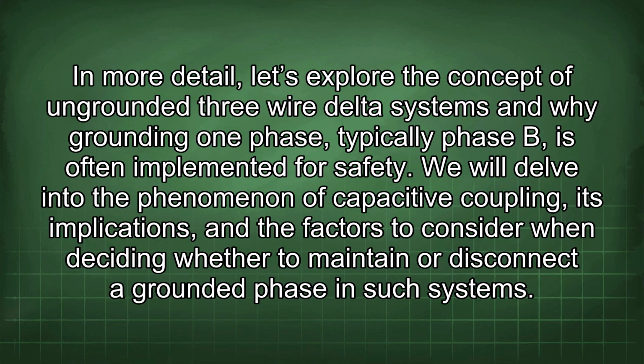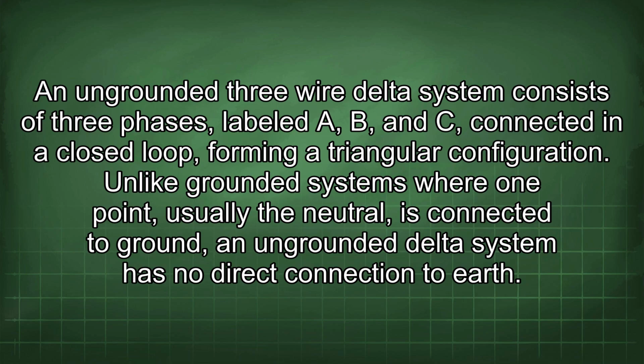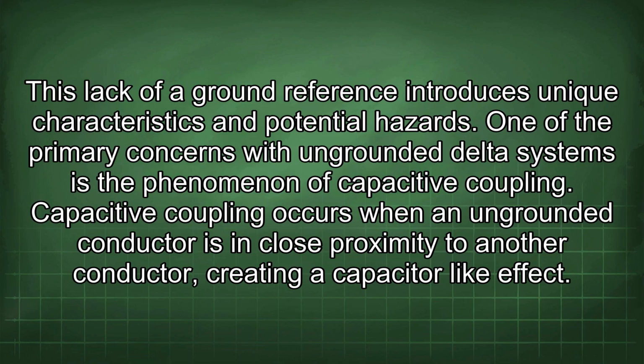In more detail, let's explore the concept of ungrounded three-wire delta systems and why grounding one phase, typically phase B, is often implemented for safety. We will delve into the phenomenon of capacitive coupling, its implications, and the factors to consider when deciding whether to maintain or disconnect a grounded phase in such systems. An ungrounded three-wire delta system consists of three phases, labeled A, B, and C, connected in a closed loop, forming a triangular configuration. Unlike grounded systems where one point, usually the neutral, is connected to ground, an ungrounded delta system has no direct connection to Earth.